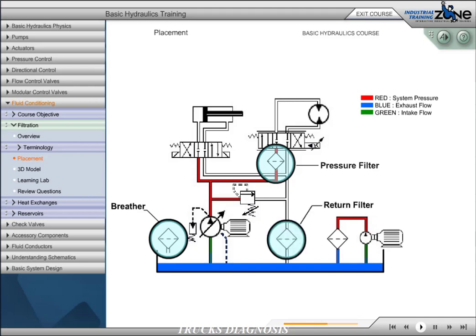Return filters best provide for maintaining total system cleanliness depending on their micron rating. They can trap very small particles before they return to the reservoir, and must be sized to handle the full return flow from the system. A kidney loop or offline filtration is often required when fluid circulation through a return filter is minimum. Being independent of the main hydraulic system, offline filters can be placed where they are most convenient to service or change, and normally run continually.